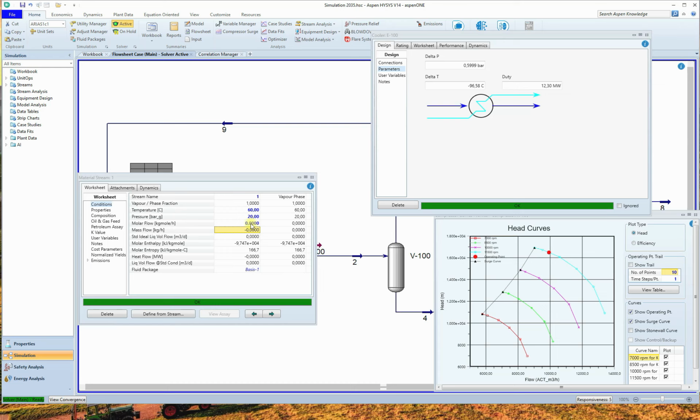Maybe not 100% accurate, but the error should be very small based on my experience, and also on checking with calculations using HTRI and other software. I found it a very reasonable pressure drop calculation.